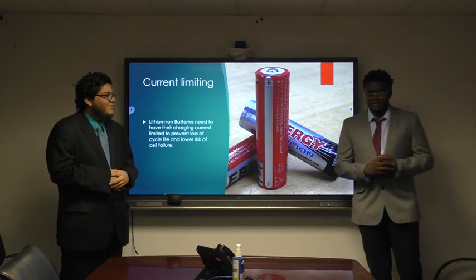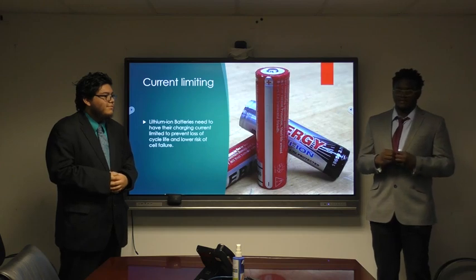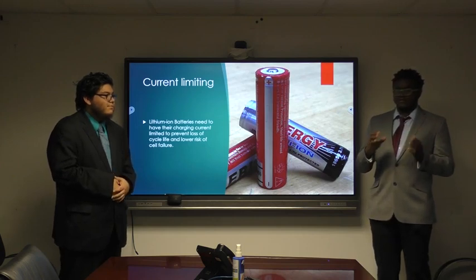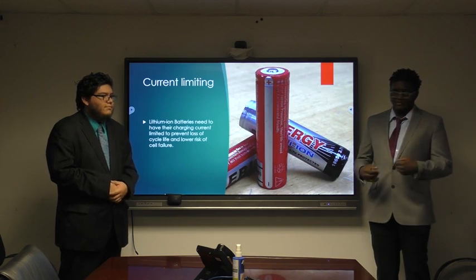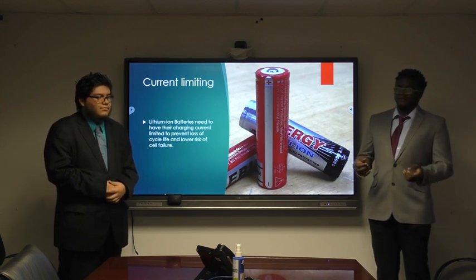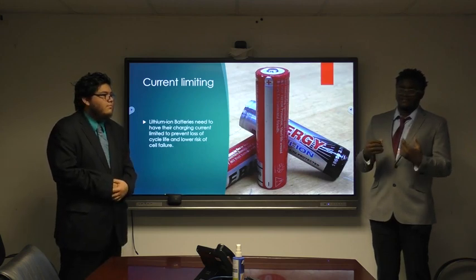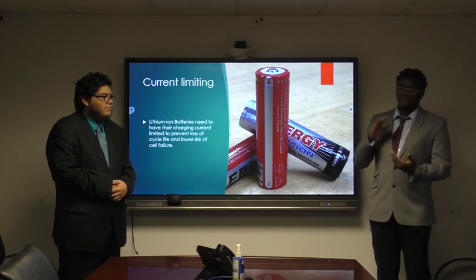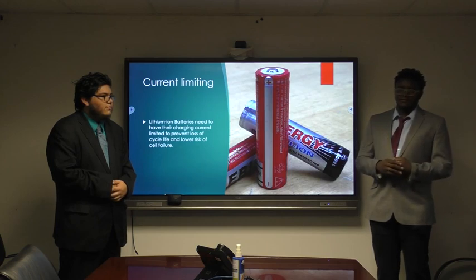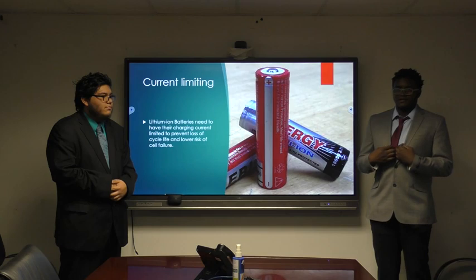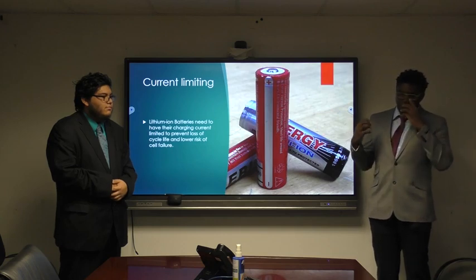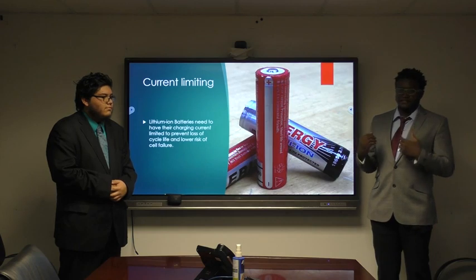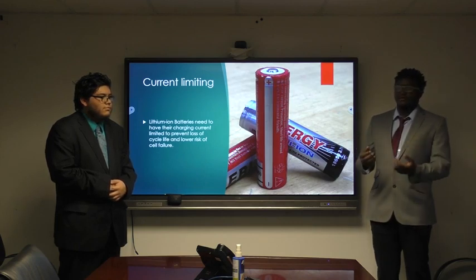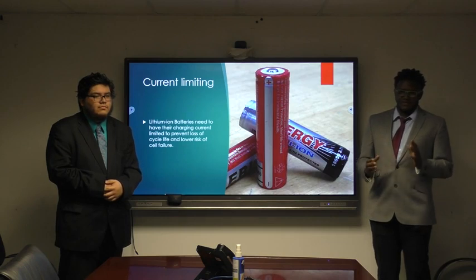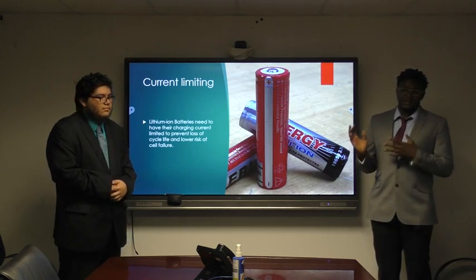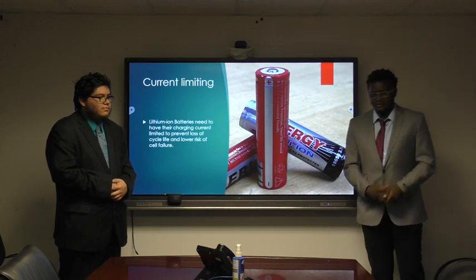With overcurrent situations, you start running into more of a thermodynamic limit, where you're running too much current, but the cell's electrolyte cannot pass enough lithium ions to each side of the battery to sustain the amount of current you're pulling from the battery. The reason we have this current limiting is so if there's a case of overdraw or overcurrent demand, we can limit and stop the load from destroying the batteries or causing a larger safety issue.